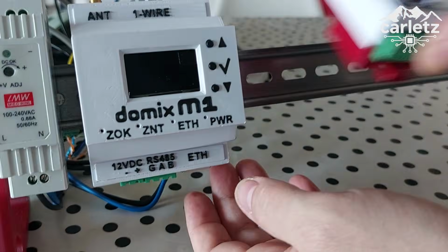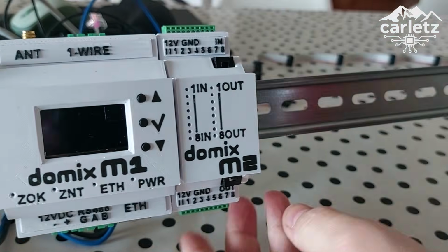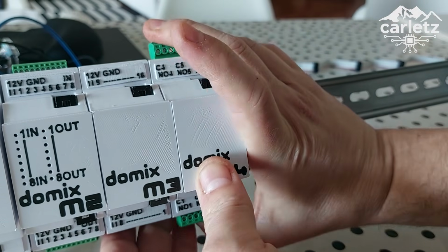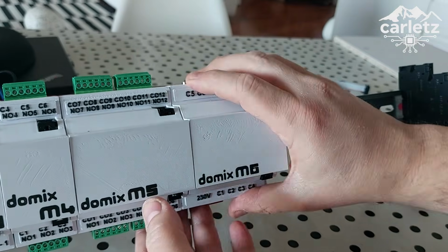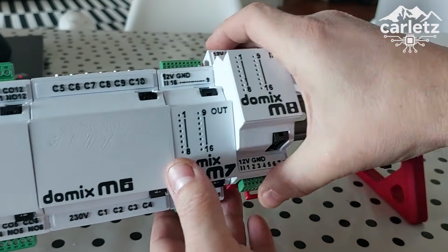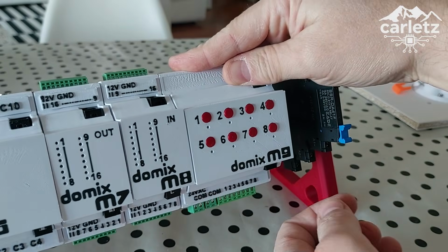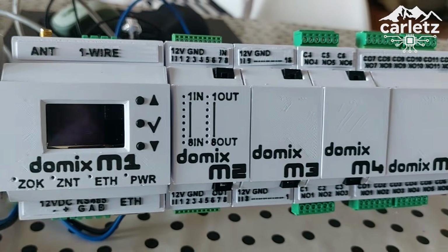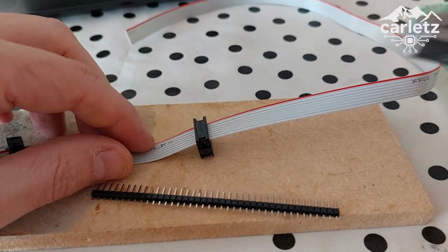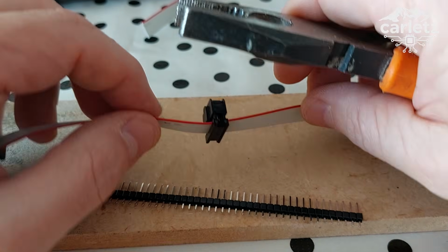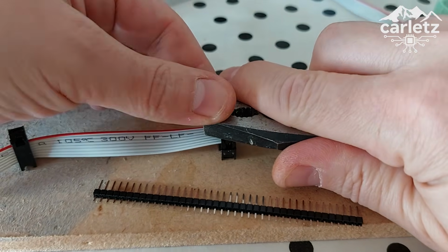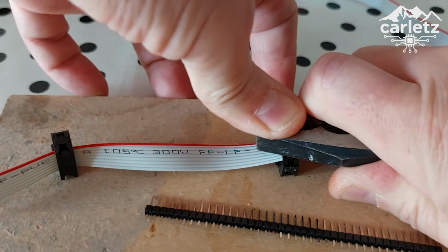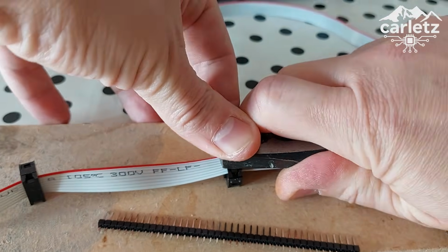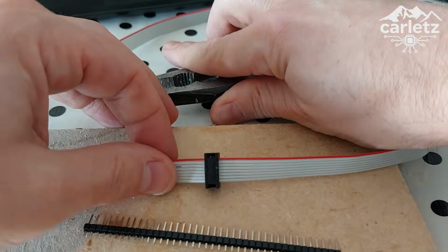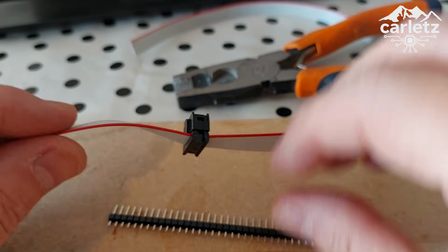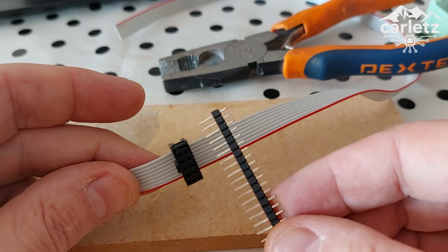Assembly is straightforward once you have all the parts ready. Each module snaps onto the DIN rail, and the modules are connected to each other via a flat IDC cable, an 8-pin ribbon cable with IDC connectors that you crimp yourself to exactly the length you need. I specifically chose IDC flat cables over pin headers for a few reasons. Pin headers are fragile in tight cabinets. One wrong movement and you bend a pin. Flat cables are much more forgiving, easier to route, and easier to disconnect one module at a time without disturbing the neighbors on the rail.